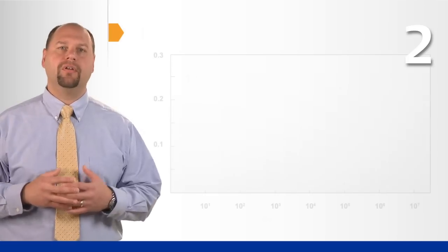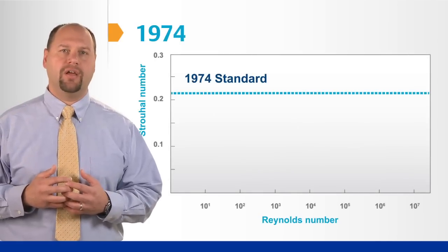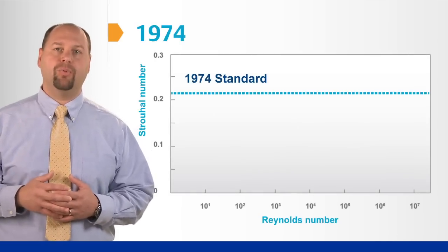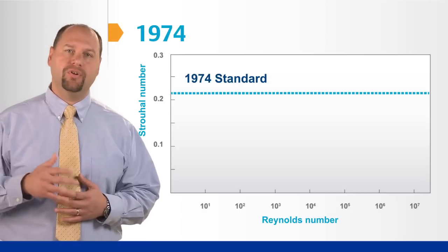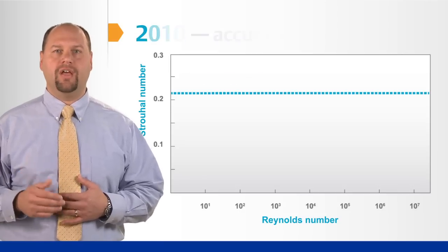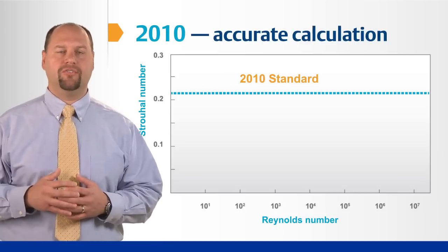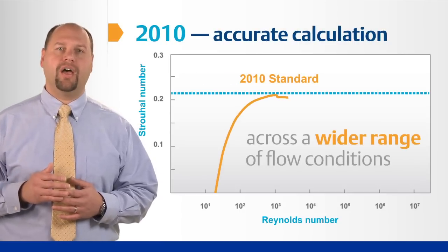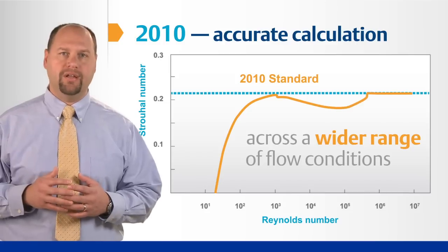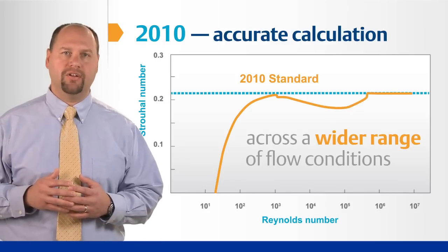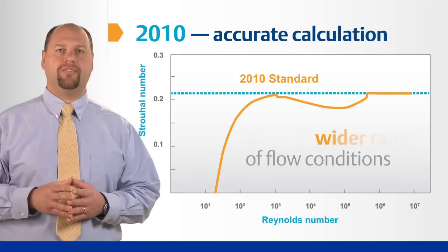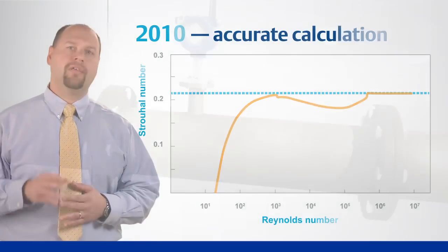Second, the Strouhal number, used to calculate the vortex shedding rate, was a set value of 0.22 in the previous standard. The new standard calculates the Strouhal number. This allows the thermowell design to be better fitted to the process conditions to minimize error and shorten the response time.